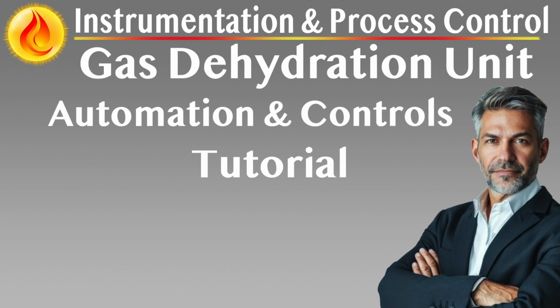Glycol side control parameters. Lean glycol injection temperature. A temperature control loop ensures glycol is at least 3 to 6 degrees Celsius above the inlet gas temperature, avoiding retrograde hydrocarbon condensation. High temperature alarms prevent glycol degradation. Low temperature alarms guard against inadequate dehydration.